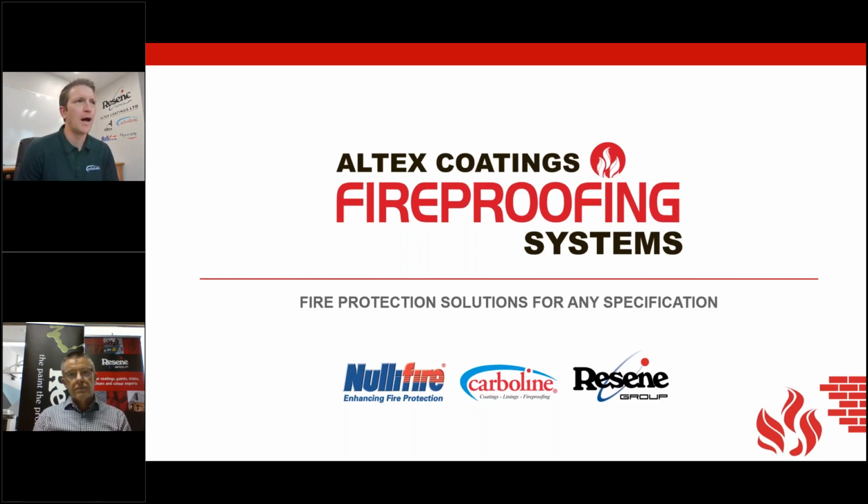The second part of the query there with regards to exceeding film build. Yes, there is a limitation to your maximum film build for your intumescent coatings. That is for the maximum tested value for a particular structural member. So for a hollow section or a UB or UC type section, they each have their maximum applied film build. That's usually you find from the 120-minute loading tables. So you're effectively looking at film builds that are in excess of 6,000 to 7,000 microns, so 6 to 7 millimeters. So if you've got your fire rating that is only sitting at a 30-minute rating, you're only staring down the barrel at 200 to 400 odd microns. There's no way that you're going to even get close to 6,000 to 7,000 microns unless you like wasting paint.